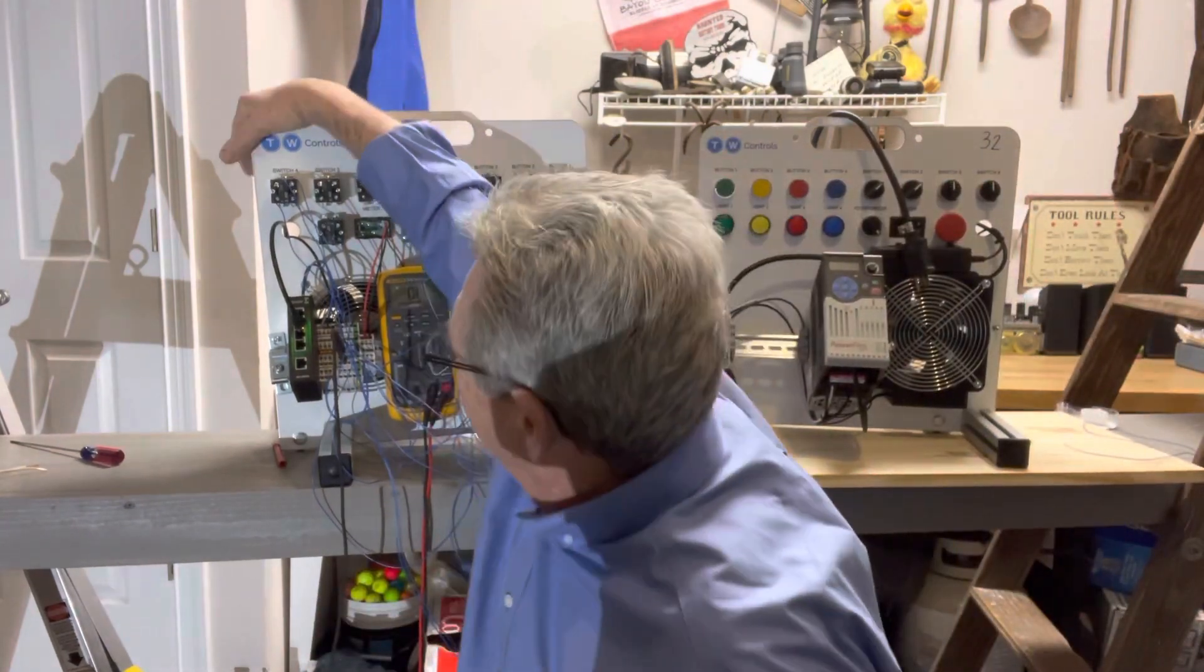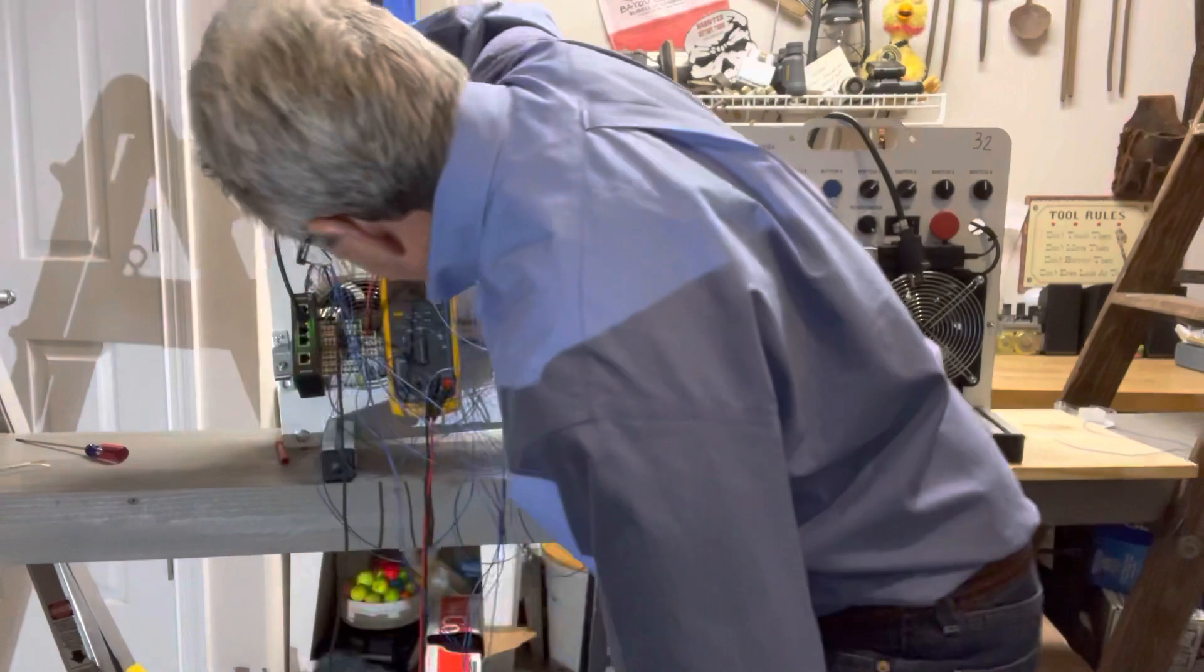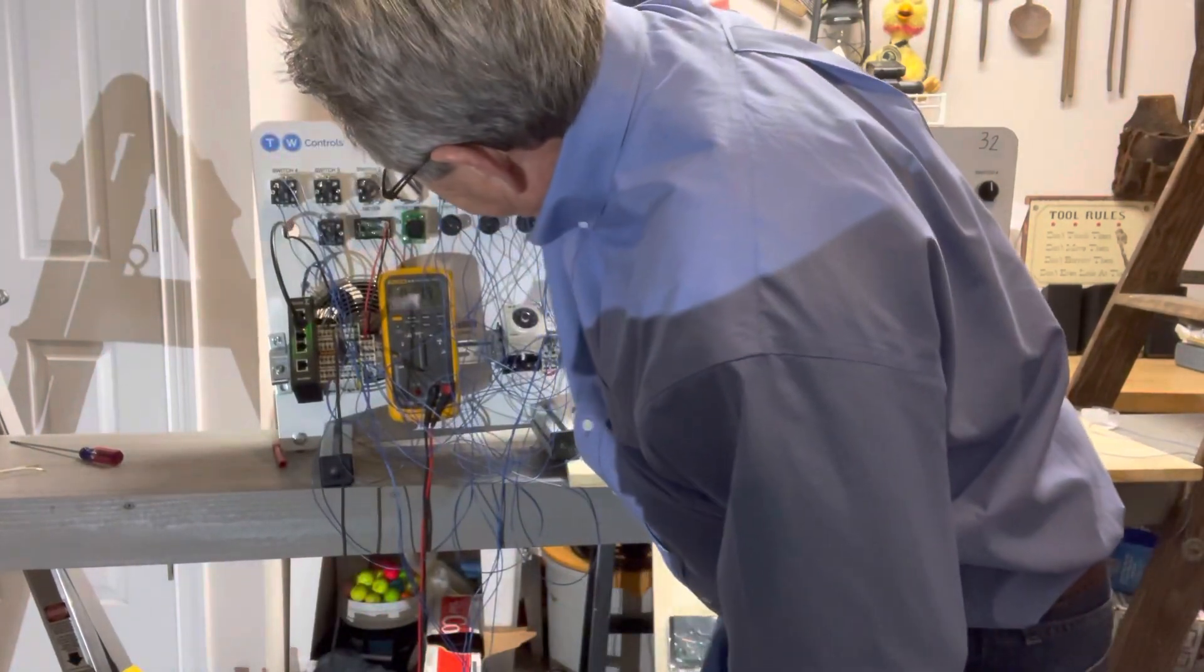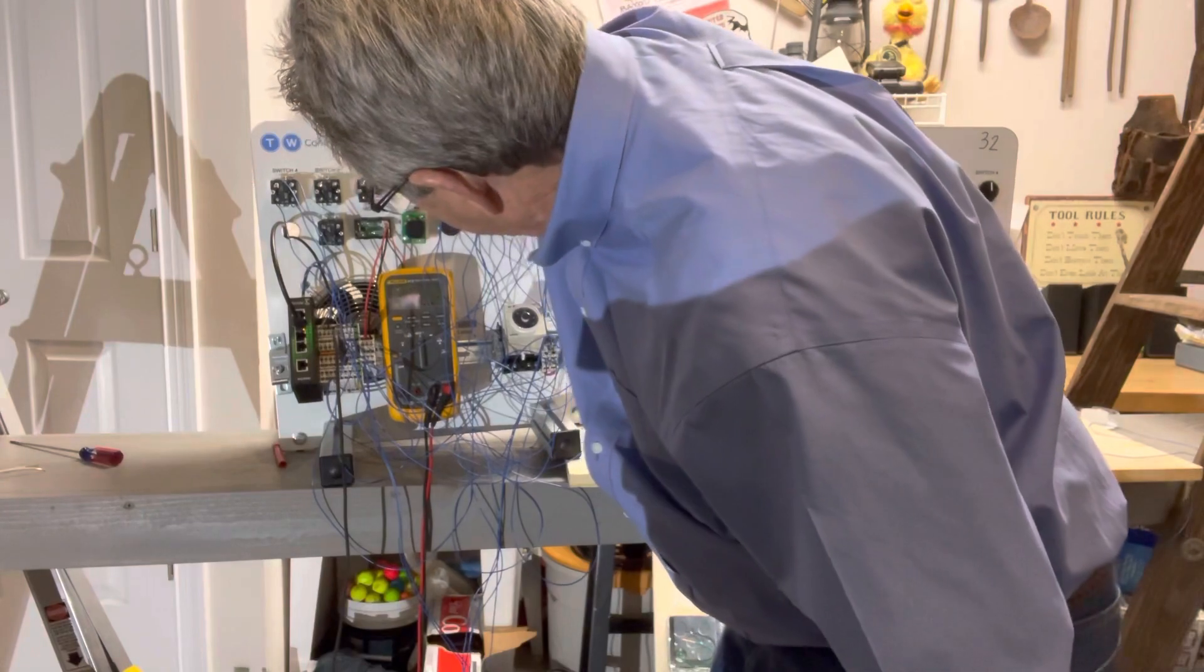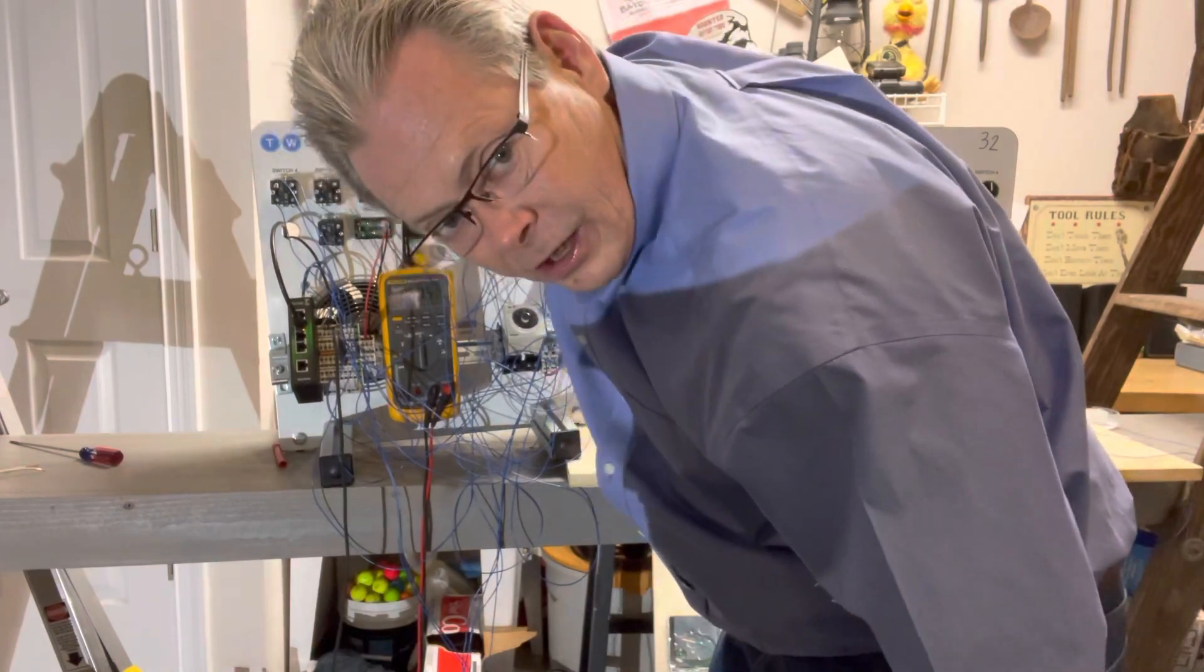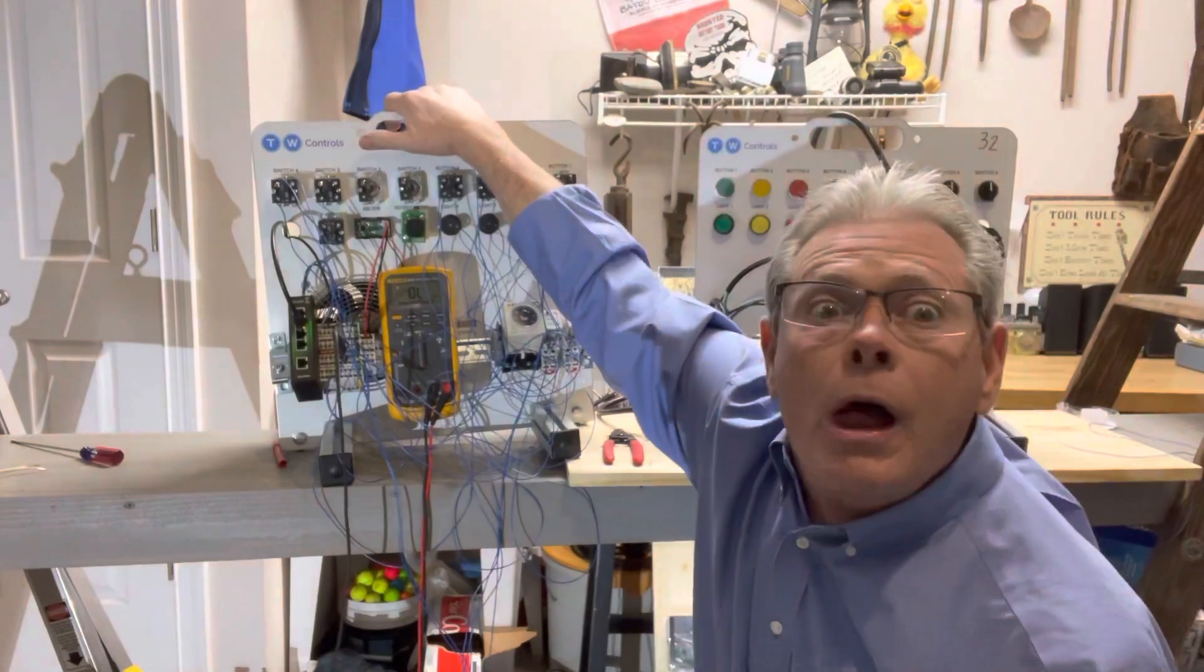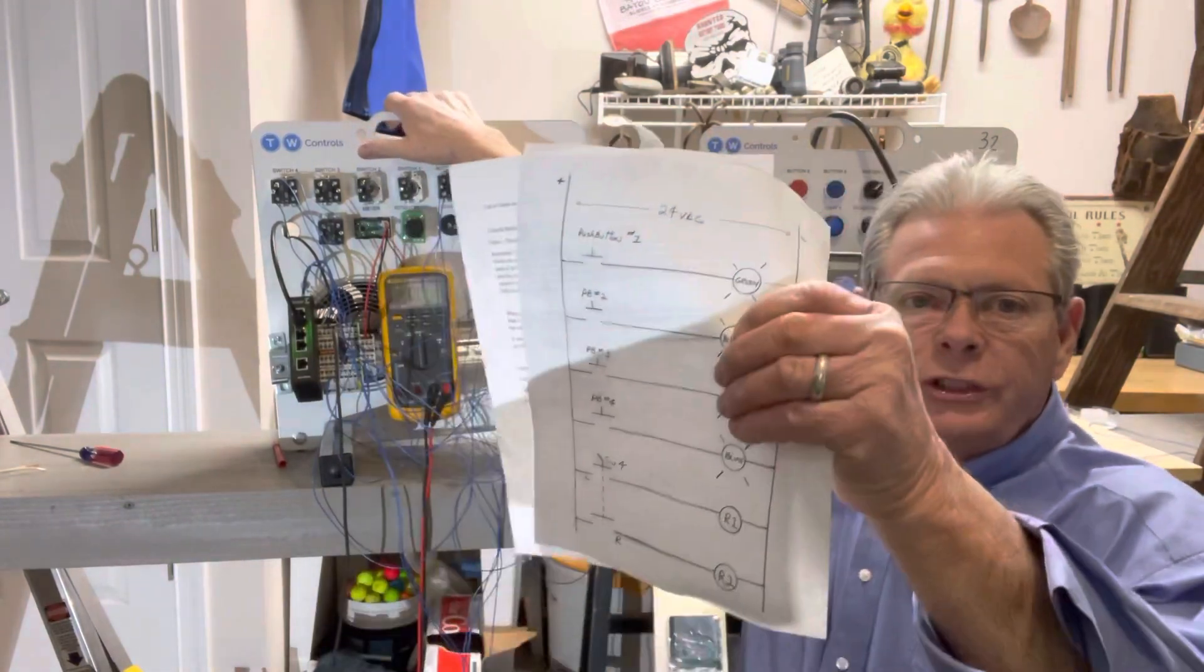So when I turn the top of it to the left, 700 ohms. Turn the top of it to the right, 600 ohms. Turn it to the center, OL. That's what we should have. That agrees with our print.